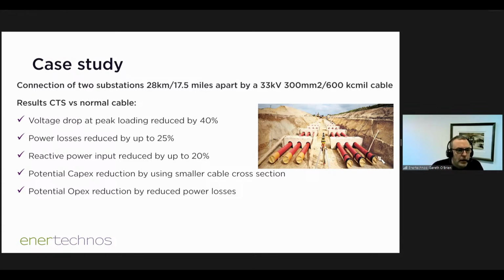It's up to you. As for reactive power input, in this particular model we were looking at a wind farm that was pulling 10 megavar of reactive power to support its load, and that went down to zero. So in that circumstance, the self-compensated nature of the export cable was able to replace a reactor.